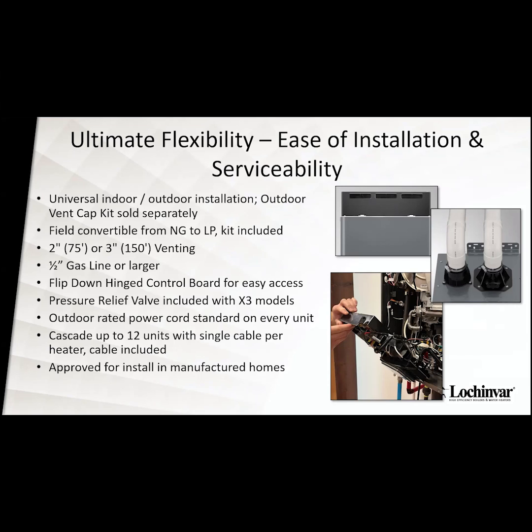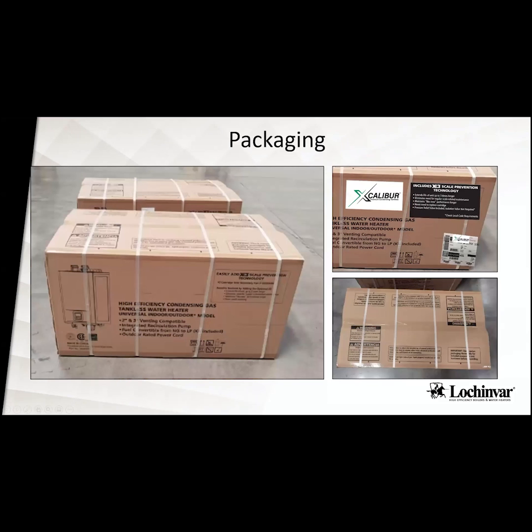The cord that is attached to this unit is an outdoor rated cord, although we won't be putting it outside in Montana. You can also cascade and common vent up to 12 units with just the cable that is provided inside of the unit. Each unit does come with a communication cable. If you're just installing one unit, you would just toss that. But you can actually put 12 of those communication cables together, which we'll talk about a little more in the presentation. So this is how the tanklesses come.